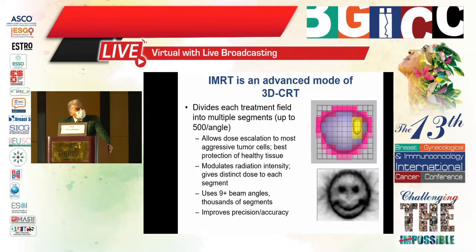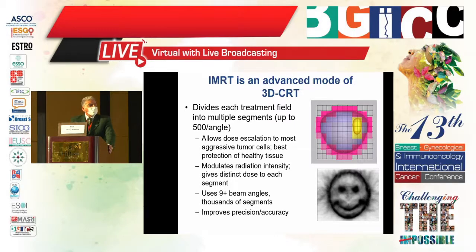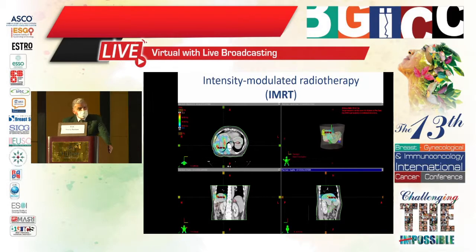This is an IMRT plan. It is an advanced mode of 3D conformal therapy. It divides each treatment field into multiple segments — up to 500 segments per angle — allowing dose escalation to the most aggressive tumor cells and best protection of healthy tissue. It modulates radiation, giving a distinct dose to each segment, uses 9 or more beam angles and thousands of segments, improving precision and accuracy. I would like to demonstrate the capabilities and power of precision of IMRT.